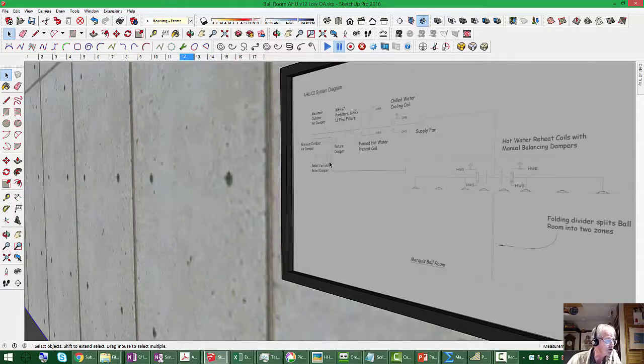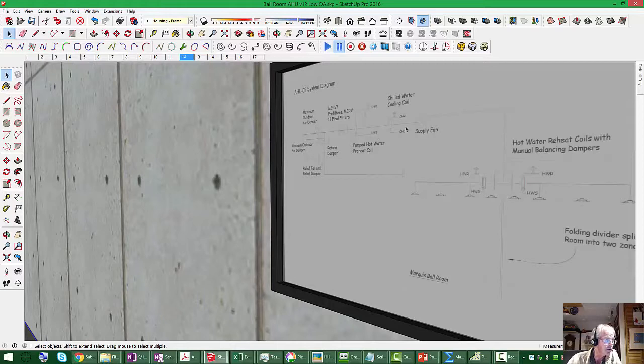And so if you look at the system diagram, basically, there's a supply fan, which is at the end of the unit. So basically, this is the stuff that's in the mechanical room. And here's the ballroom. It's a large ballroom with a folding divider, is what that note says. And there's 2 hot water reheat coils with manual balancing dampers, but there's no volume control equipment. So unless there's been a retrofit of some sort since this drawing was hung on the wall, which is a possibility, basically this is configured to be a constant volume system.